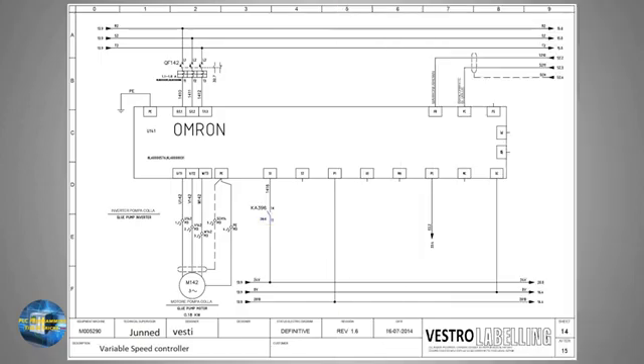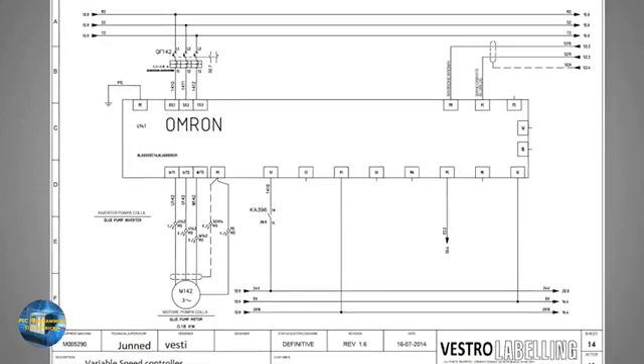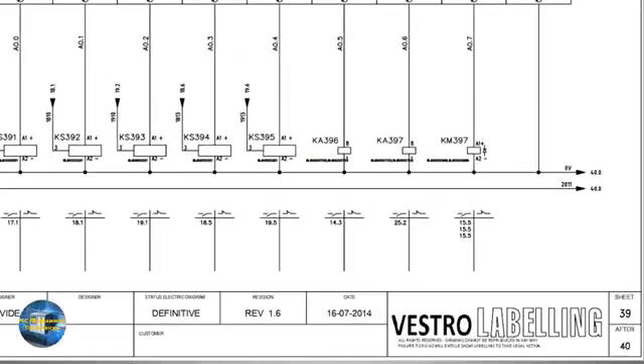Mostly, if any tag starts with KA, this means that it is a relay or a small control contactor. To find this relay, we have to see the first two digits of the tag KA396. Yes, you guessed it right. We will go to sheet number 39, and we have to look in column number 6. Let's go to sheet number 39.